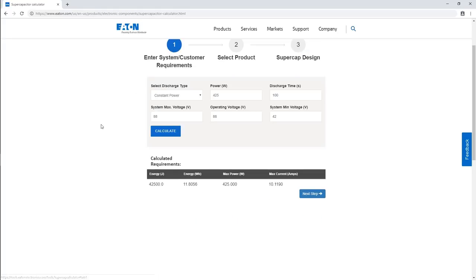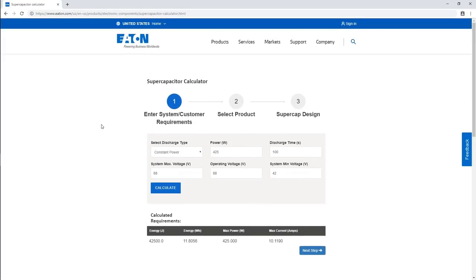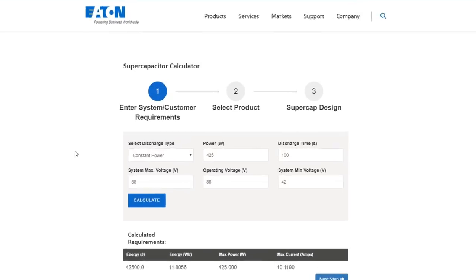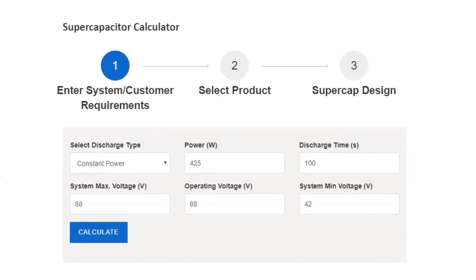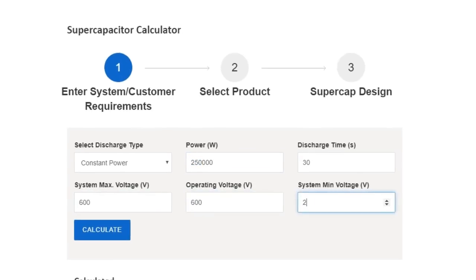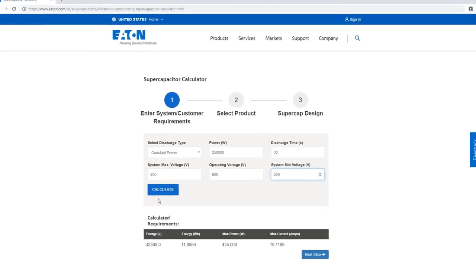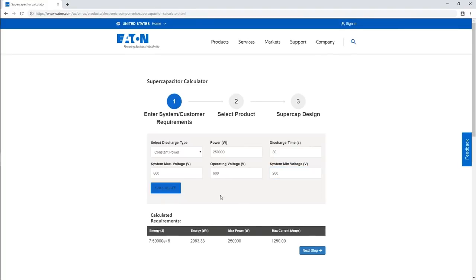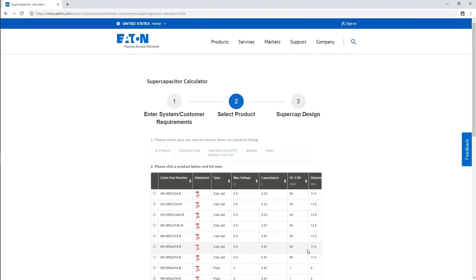Now let's consider backup power for a microgrid. In this application, we need a constant 250 kilowatts for 30 seconds to transition from our PV source to the grid or a backup generator. This application is going to require a lot of energy storage, and while you could build a solution with a massive array of individual cells, we've already done that with our module products, so I'm going to select a module to keep things simple.